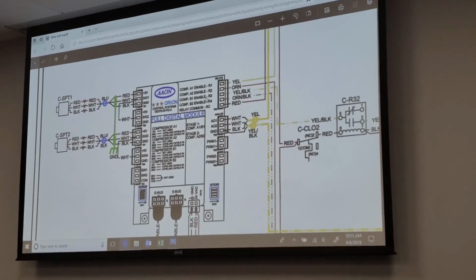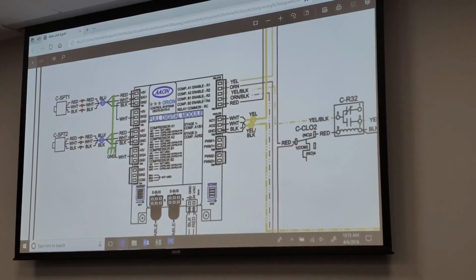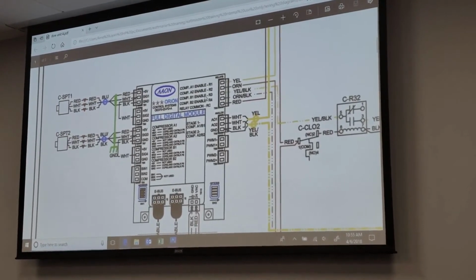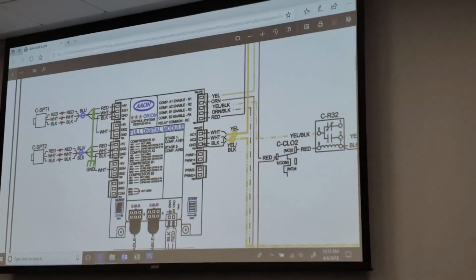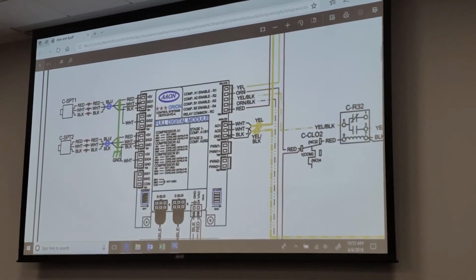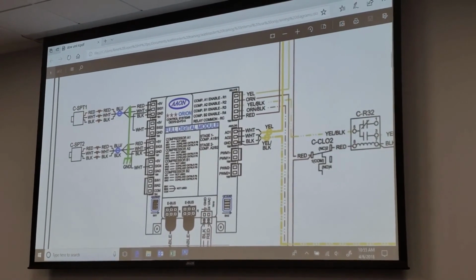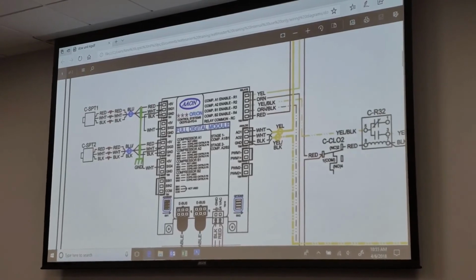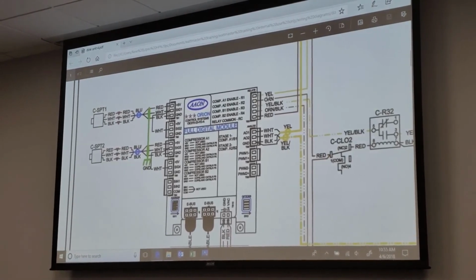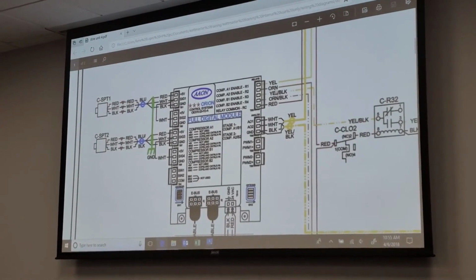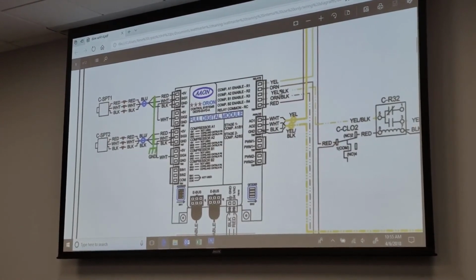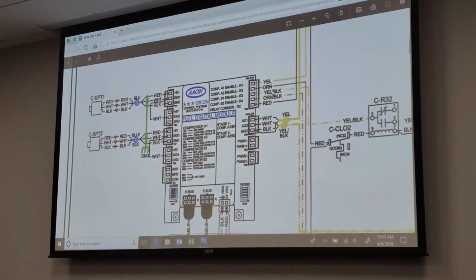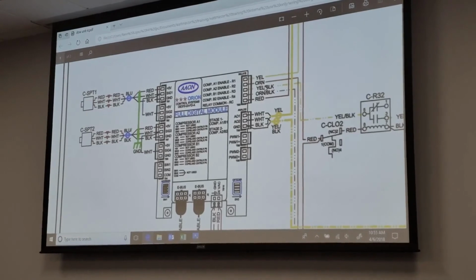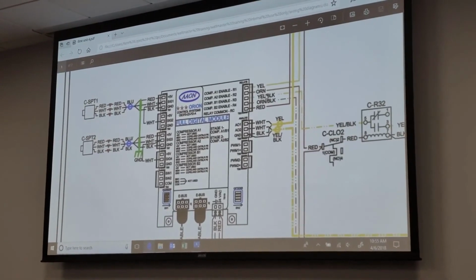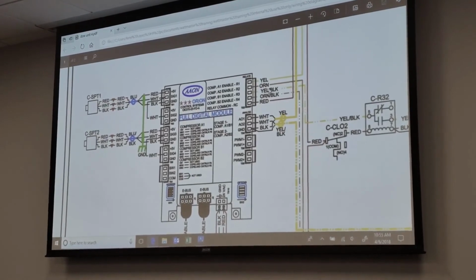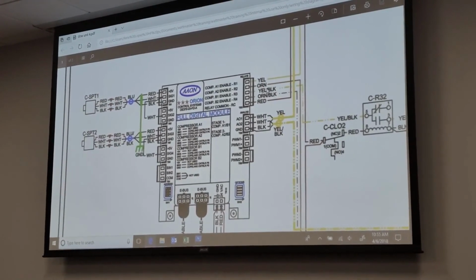Well, we had a full digital module go bad. They wired it back exactly like this, and compressors 2 and 3 kept tripping out on head pressure. Well, because on the new board, the yellow wire is compressor number 1, the yellow and black is compressor 2, orange is compressor 3, orange and black is compressor 4. On the new board, these two need to be swapped because the programming logic changed. What spurred that drawing was the compressors tripping. They didn't change it on their drawing.